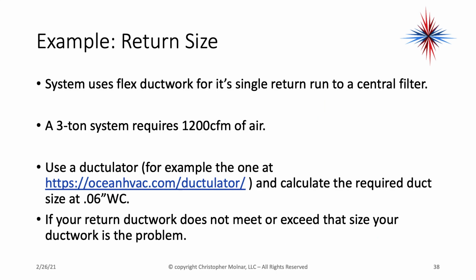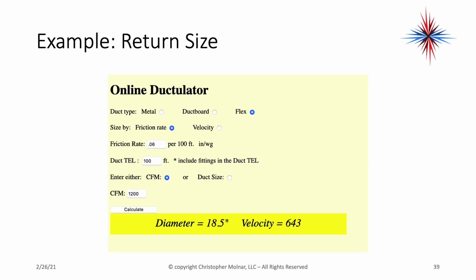Okay, system uses flex ductwork. This is an example. Single run to a central filter. A 3-ton system requires 1200 CFM of air. Use a ductulator. It's an airflow calculation tool, and calculate the required ductwork at 0.06 inch water column. It's what I'd like to have for my return. If my return ductwork does not meet or exceed that size that comes up on the ductulator, your ductwork is the problem. So this is an example of the online ductulator.